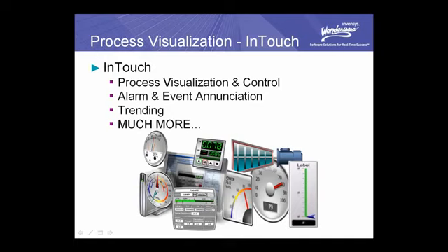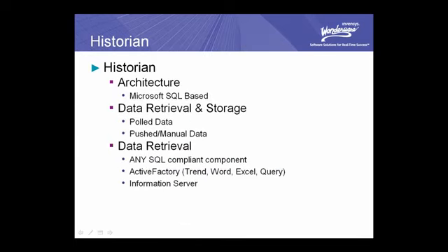While I'd like to camp out here for quite a while detailing how these graphics can be designed and used to greatly simplify application development, it's time we move on to our next component of System Platform, the Wonderware Historian. The Historian product is Microsoft SQL based and actually extends the capabilities of SQL Server. It can log tremendous amounts of data over long periods of time, and it compresses the historized data with a lossless algorithm to ensure you can store a lot of data over a lot of time in the least amount of space and not lose anything while compressing it.